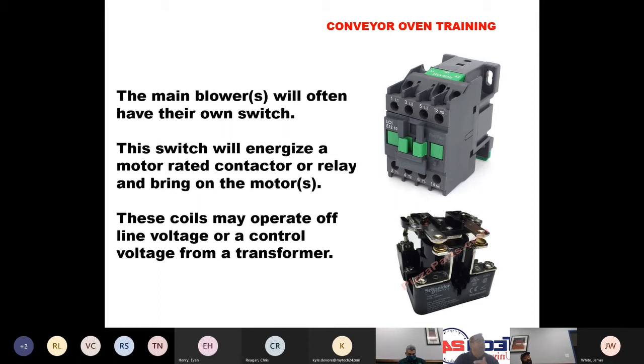Something has to energize our main blowers. This is usually going to be a contactor or a relay. This is the switch that basically energizes that motor to bring it on. Typically, these coils operate off of line voltage, but they can also be controlled by a low voltage, like a 24-volt circuit, depending on how the manufacturer is designing their oven.